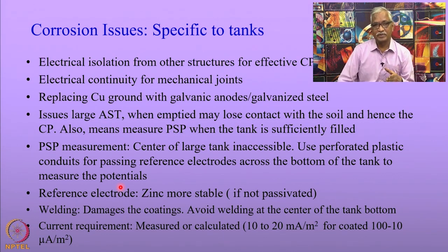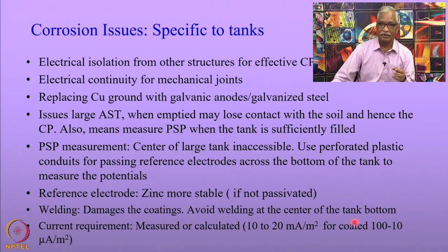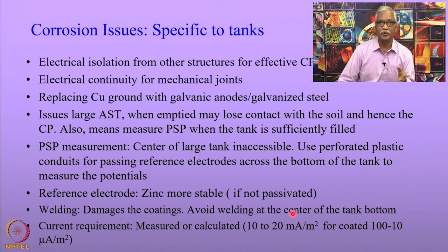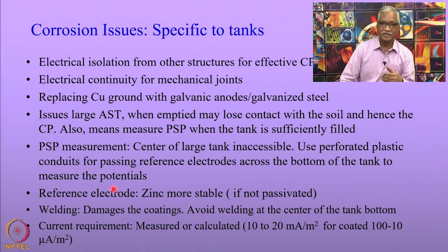Another issue specific to the tank is that during commissioning, one should avoid welding at the center of the bottom of the tank, but that is easier said than done. When welding is done, the coating gets damaged and the current requirement to protect the tank at that location becomes very high.